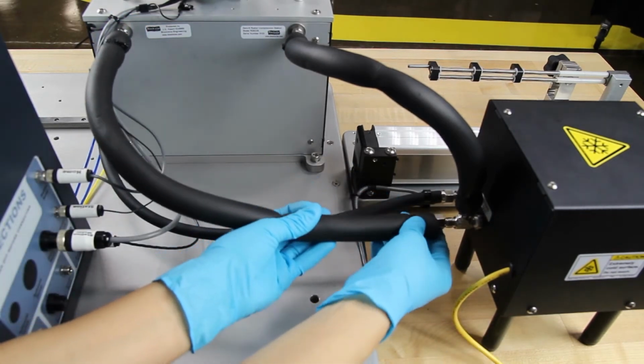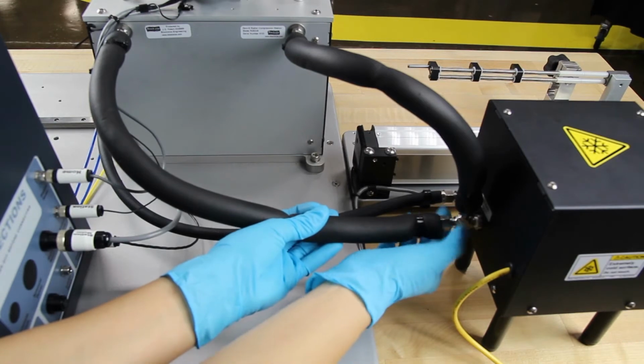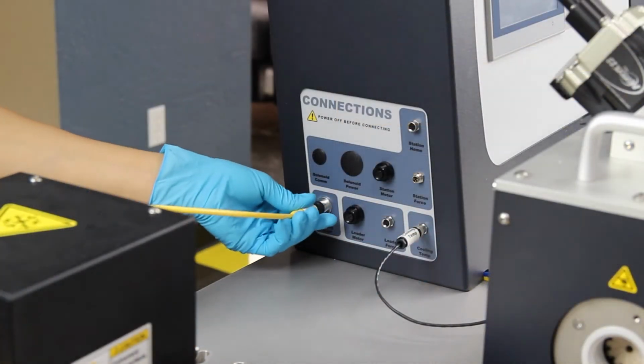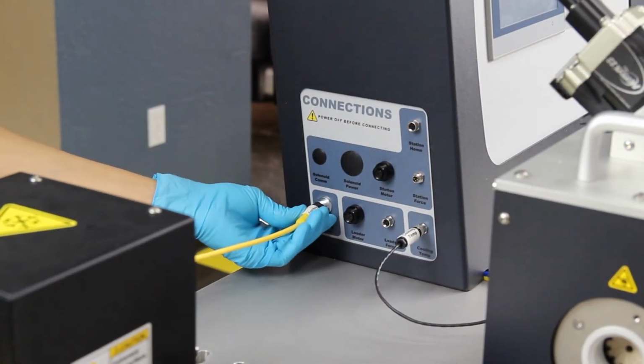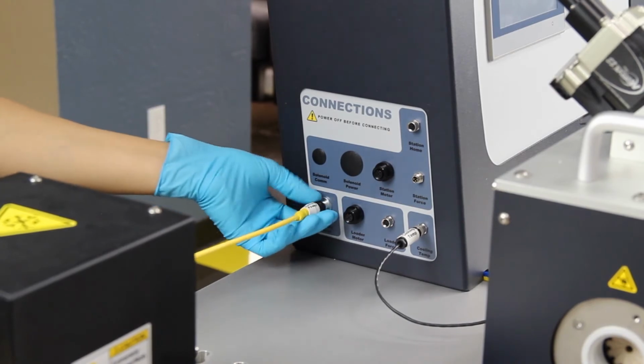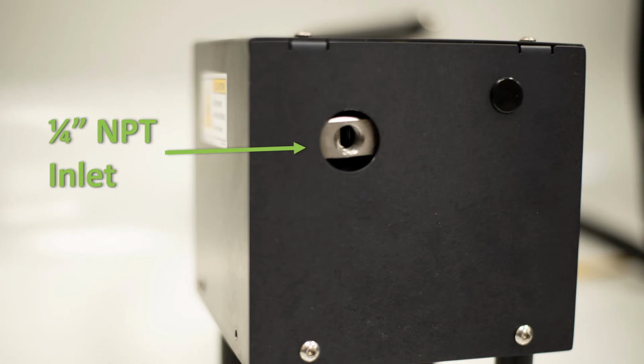Lastly, you'll need to connect the cooling box to the cooling power connection on the side of the machine. Remember to always have the machine turned off when connecting or disconnecting. You can now connect your liquid nitrogen source to the cooling box. The inlet is a 1/4 inch NPT fitting.